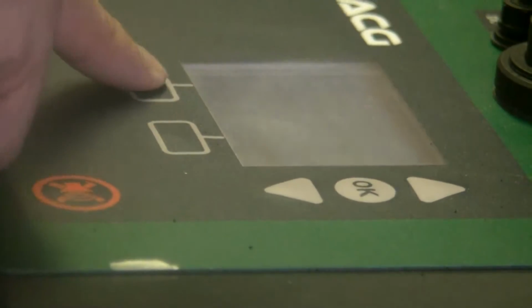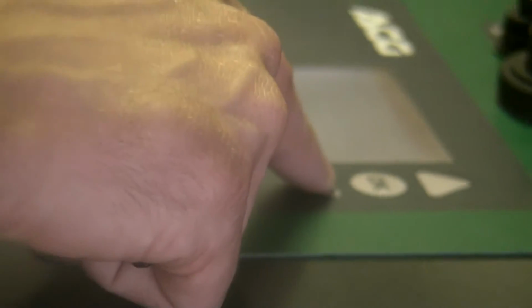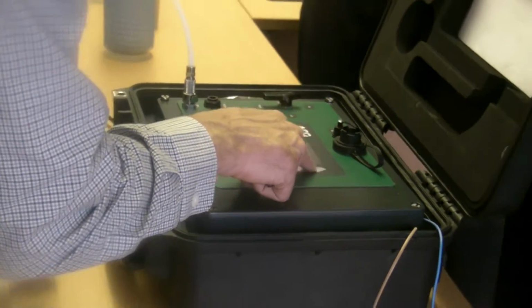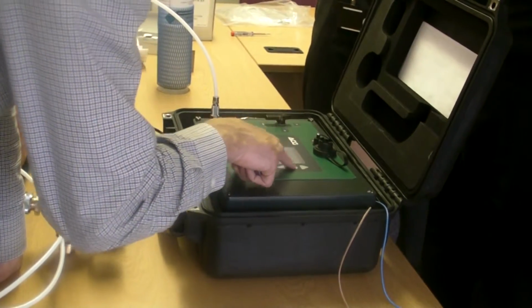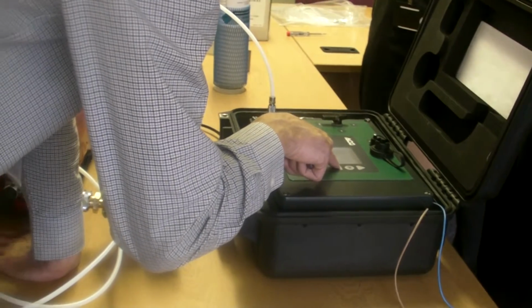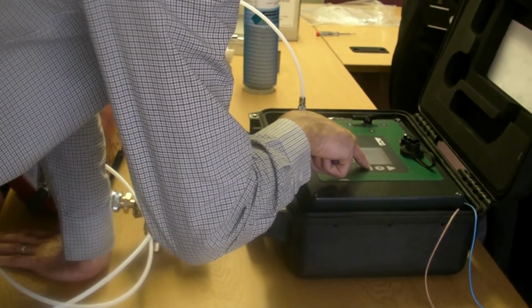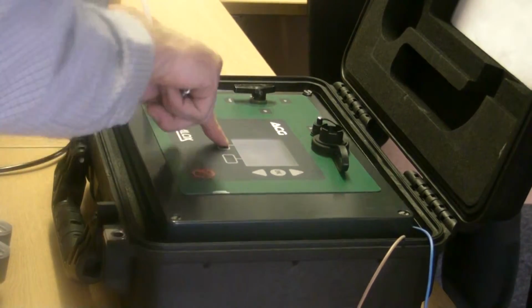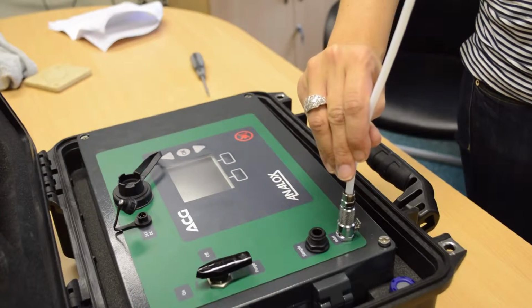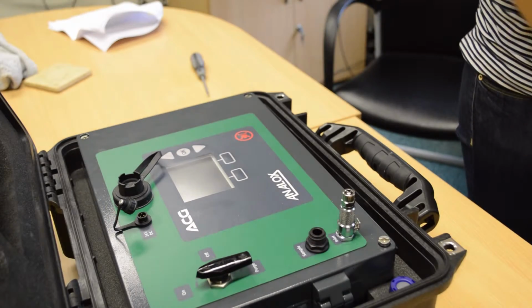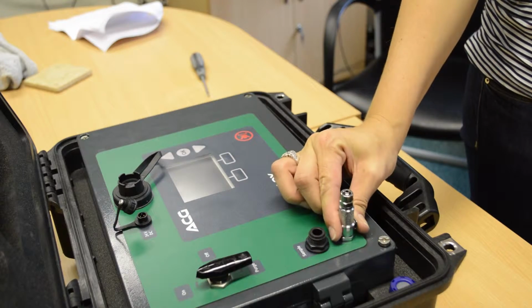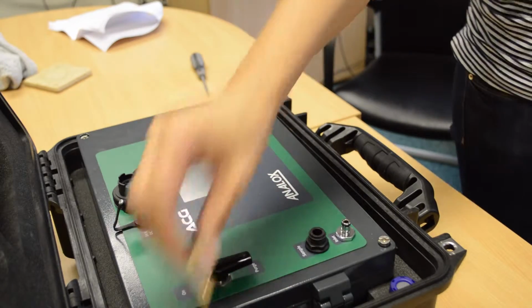To perform an adjustment from the main menu, select Calibration, then select the bottle that is currently attached by scrolling through the menu options. The calibration adjustment screen will be shown. To finish, close the valve on the bottle flow regulator and close the inlet valve on the front panel, then disconnect the calibration connector from the ACG Plus by pressing the release catch and gently removing.